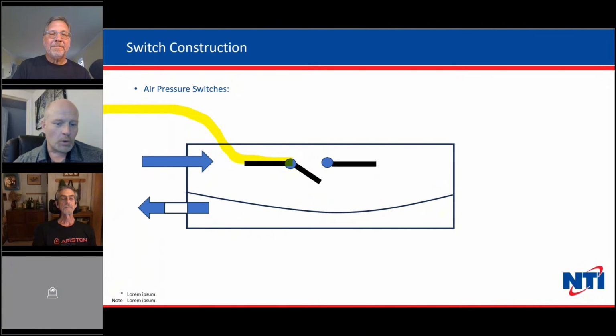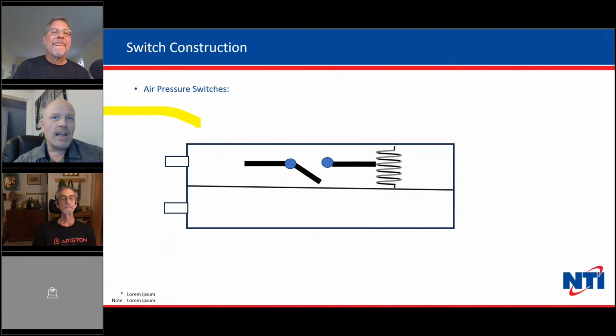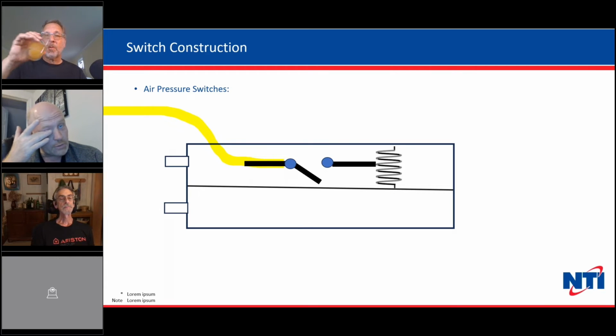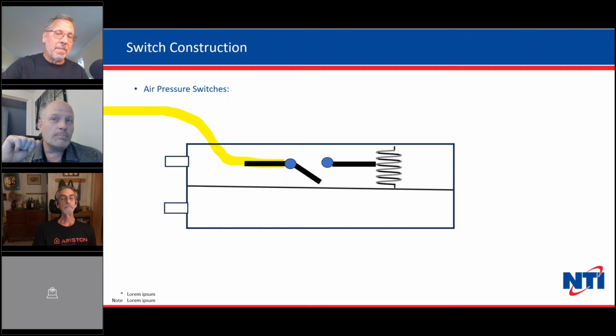Now, we don't always use the ports as you might expect. We use them in different ways depending on the product, and we'll hopefully cover that a little bit more. One thing to keep in mind is that the pressure difference between the top and bottom is really what's tripping the switch. In a lot of cases, we don't use just one or the other port, we use both. And when we use both, it means that this is a pressure differential switch. It's a bit like taking a static pressure with a differential pressure manometer: you go to two different points in the ductwork and get a static reading. That's how we use these switches in a lot of cases: it reads an intake and an exhaust. Obviously there's always a bit of positive pressure in the exhaust and a bit of negative in the intake. But if either one gets too far out of range, it can trip the switch. So look at where the tubes run. And we're going to talk about a special case where we use this as an air flow proving switch in a few minutes.